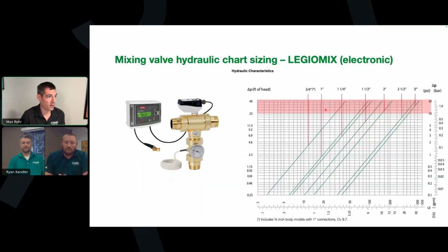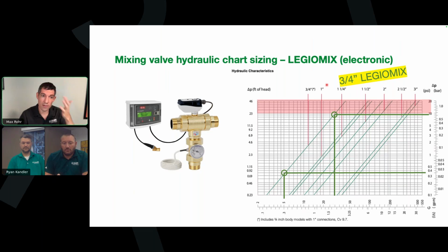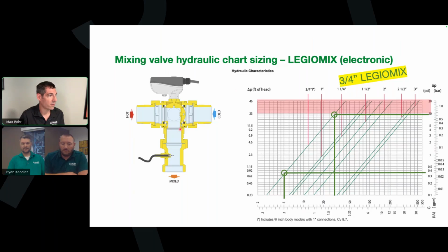So let's look at the digital mixing valve and just compare a couple things here. So 5 GPM minimum flow rate, 30 GPM maximum flow rate. In this case, I used kind of an extreme example here just to make a point. We can go through how you would make your own decision here. This would line up with a 3/4 inch Legio mix, which if you saw this in a hospital, even if it were properly sized, you might think, did you guys get that for free in a raffle? Why do you have some residential size mixing valve in this project? But this is how we would do the math to show, no, this is the right digital mixing valve for the project.